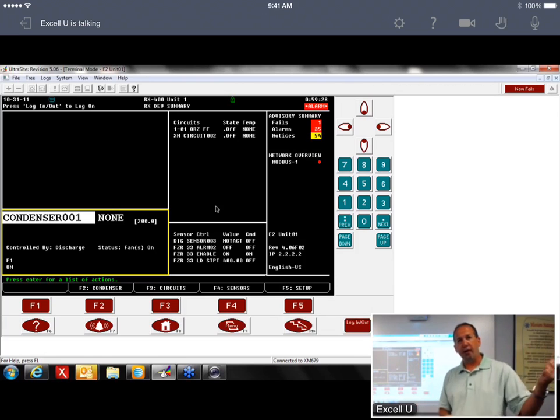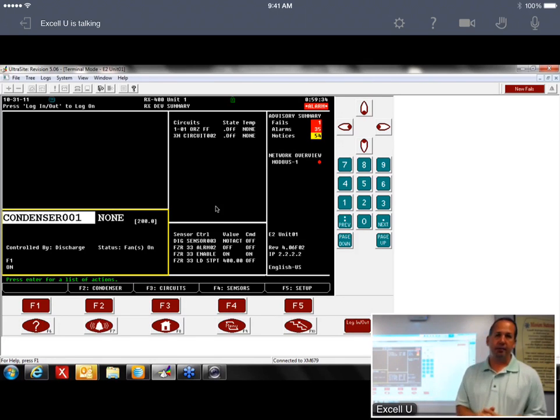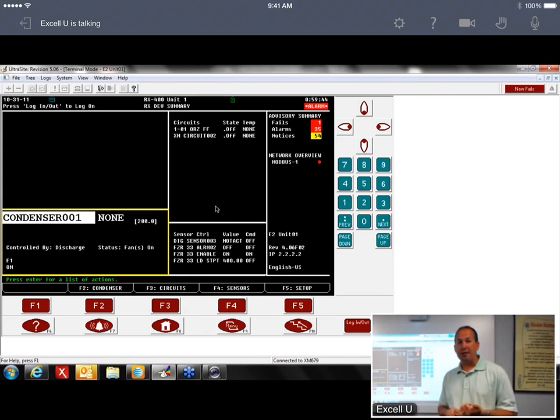Don't forget to reverse your polarity at the E2. You can do it that way, running your CCBs standalone until you eventually get them all out. But if you're still going to use some of those CCBs, you have to run a new network. So I'd only reuse the CCB network if everything on that loop is going to change to Dixell. If you've still got cases on CCB and some on Dixell, you'll have to run a new network.